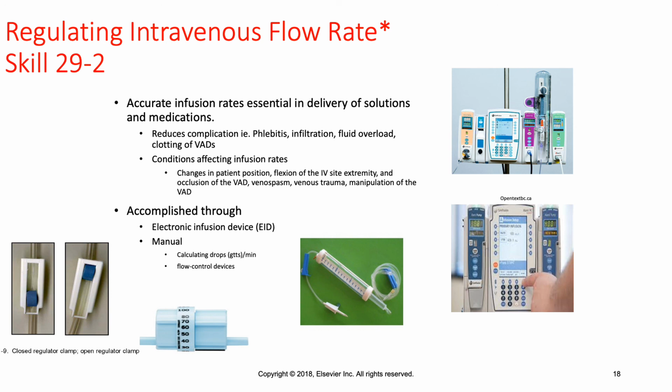So we also need to keep in mind, if we set our IV pump correctly, or if we manually adjust our roller clamp so that the patient receives the number of drops per minute that they're supposed to, what are some of those outside factors that might influence the rate of infusion? One of them is the height of the actual IV fluid bag.